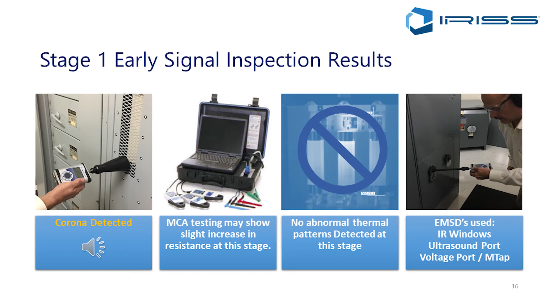So that's the one cautionary thing there. If we let it go further down the curve, maybe we start to get tracking inside that gear. Maybe we see a couple of indicators in our motor current analysis saying something's not quite right. We're not in the red zone yet, but we're starting to see things that are definitely yellow, and we want to start thinking maybe we need to take corrective action soon, or maybe we have to step up again that interval.